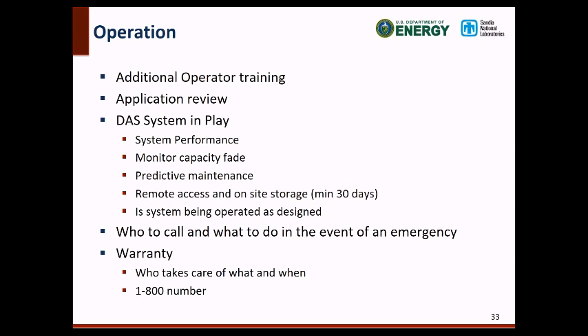You also want to make sure you are getting remote access and that the on-site storage is working too. You need to verify that you can pull out that SD card or USB drive or whatever you have in place, and it does have logging of the data on it. And then also make sure the system is being operated as designed. This is what I was talking about earlier with the application review. Make sure that if it was made for arbitrage, it's doing arbitrage. It's not trying to do frequency regulation or some other form of application.